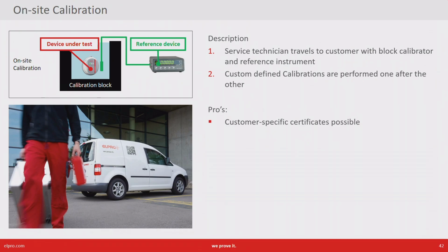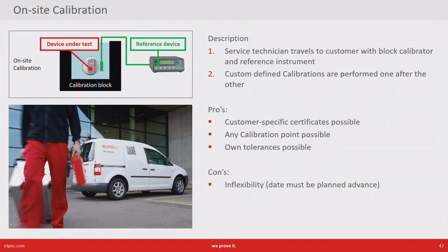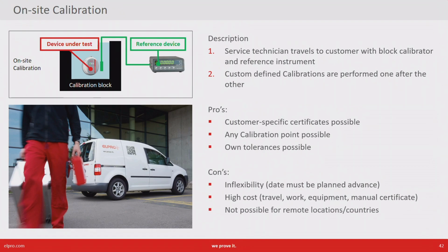The advantage of this solution is that customer-specific certificates are possible. You can choose any calibration point, and you can even have your own tolerances if you want. The disadvantage is that this is relatively inflexible, since you need to agree on a date when the service technician comes. It's relatively expensive because you need a lot of human resources and equipment, and it's not very practical for remote locations or remote countries.